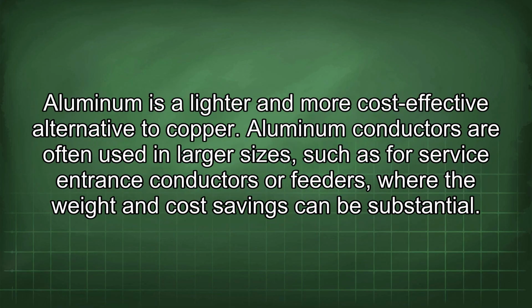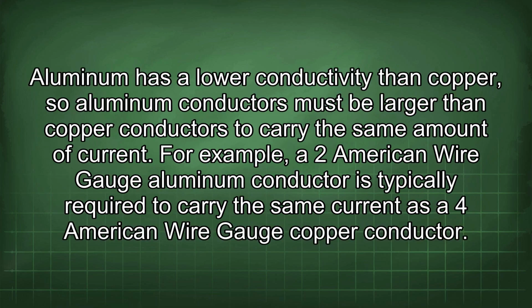Aluminum is a lighter and more cost-effective alternative to copper. Aluminum conductors are often used in larger sizes, such as for service entrance conductors or feeders, where the weight and cost savings can be substantial. Aluminum has a lower conductivity than copper, so aluminum conductors must be larger than copper conductors to carry the same amount of current. For example, a 2 American wire gauge aluminum conductor is typically required to carry the same current as a 4 American wire gauge copper conductor.